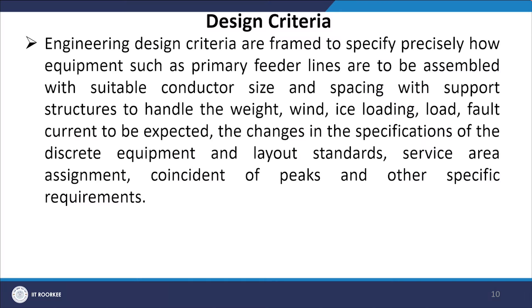Engineering design criteria specify precisely how equipment such as primary feeder lines are to be assembled, with suitable conductor size and spacing, support structures to handle weight, wind and ice loading, load, and fault current. Changes in specifications cover discrete equipment, layout standards, service area assignment, coincident peak and other specific requirements. The power utility shall prepare an operational code to incorporate all criteria and standards of distribution system operation.